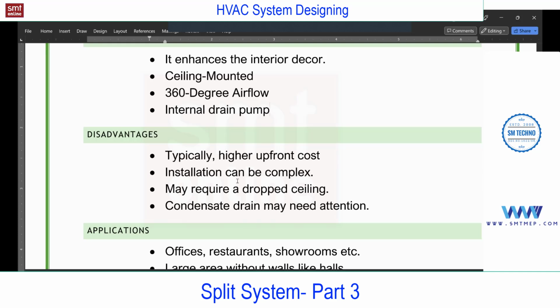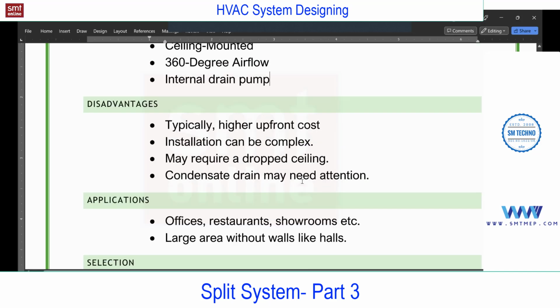For example, if you purchase 1.5 or 2 TR high wall, compared with the cassette, you can expect 25 to 30% higher in cost. Okay, because the manufacturing of that coil, the coil shape is different, and the unit. So mostly cost point of view, this is expensive. Nearly 25 to 30%. Installation can be complex. Complex means they need to align with the proper false ceiling. Sometime or many time you'll find the gap between this panel and the false ceiling. So they must take care of this proper level, and this drain pipe they must connect without any leakages.